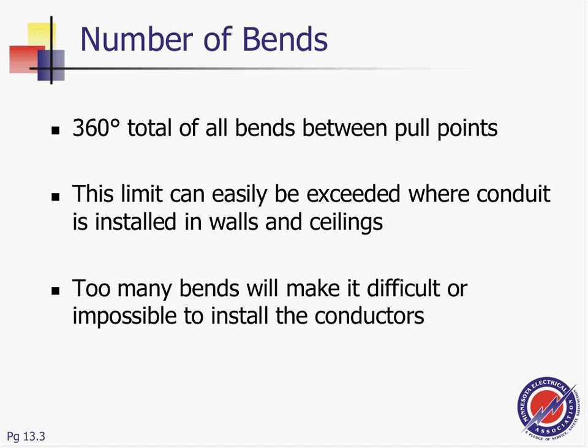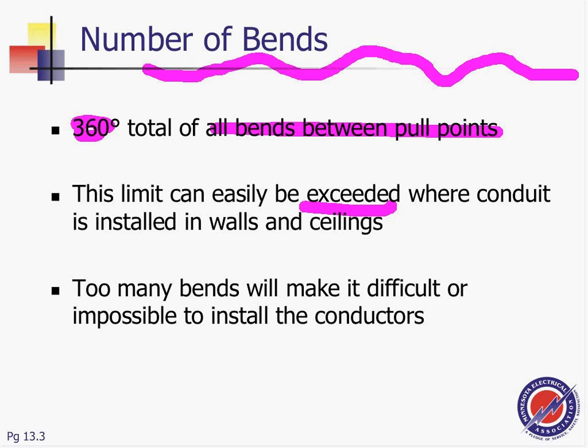My friend, I'll be repeating myself from last week because we are dealing with conduits and rules for conduits are identical. For example, how many bends can you do between pull points for any conduits? Well, 360 degrees. Doesn't matter if it's a flexible conduit. Doesn't matter if it's a non-flexible conduit. No, we cannot have more than 360 degrees between pull points. Otherwise, you have to put in a pull point. The problem with flex, guys, is that it's easy to exceed it because flex moves, it's a flex, so it moves. Look at that one coming from here. Now, counting how many angles between here and here, have I exceeded? So it's so easy to exceed it with a flex, as you can see.